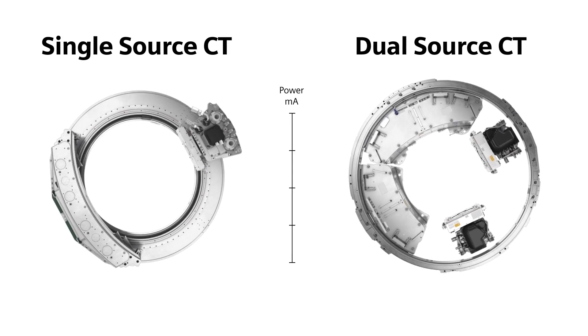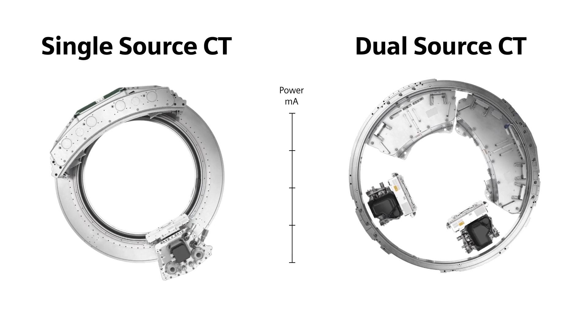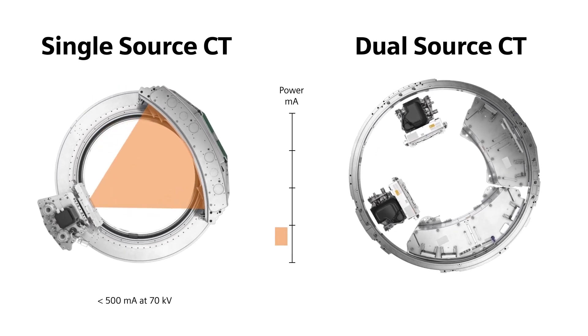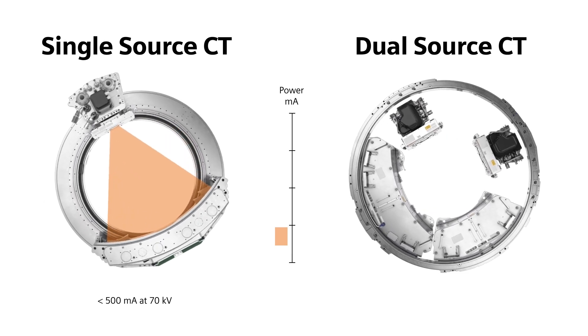Sometimes you need a lot of power to enable lower radiation dose and contrast media amounts. Most single source scanners provide a range of 500 to 800 mA, although not all at low kV levels.